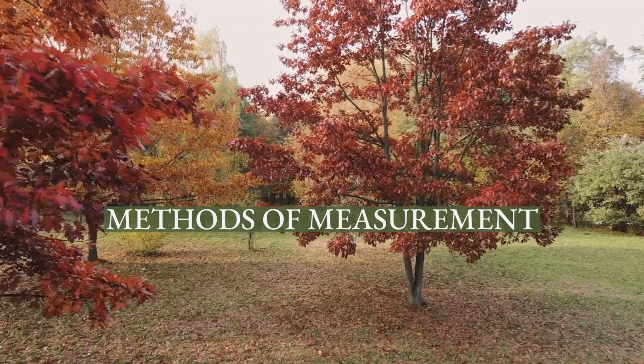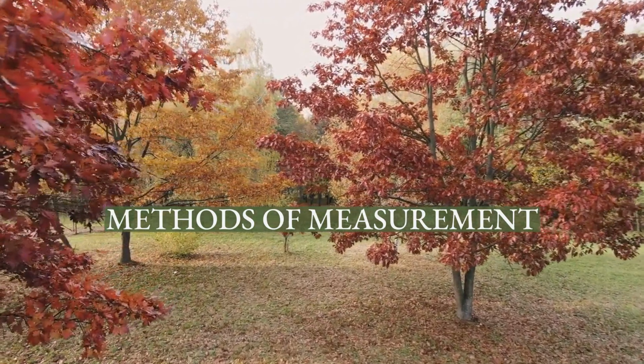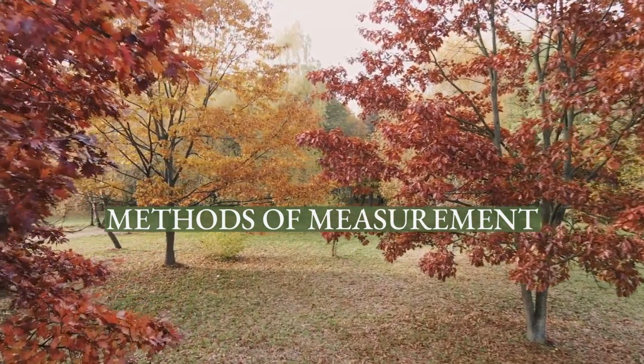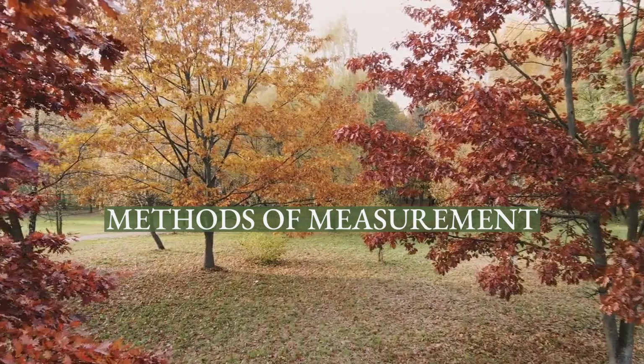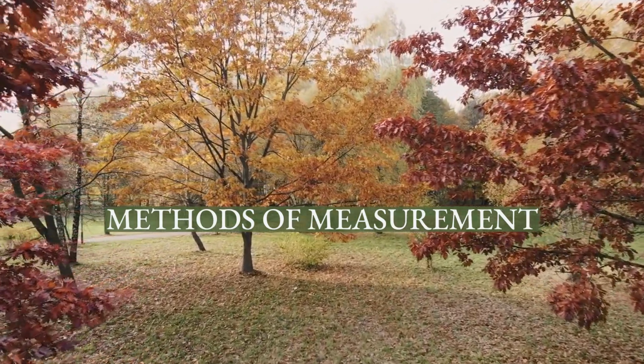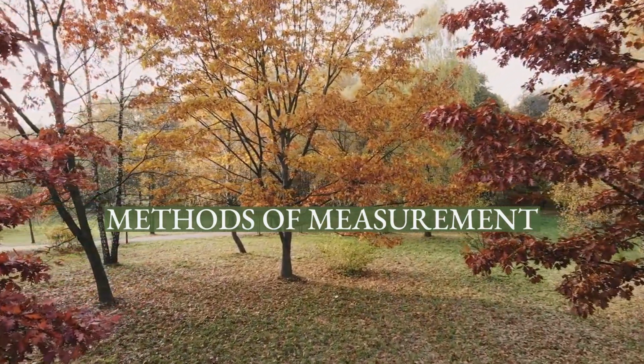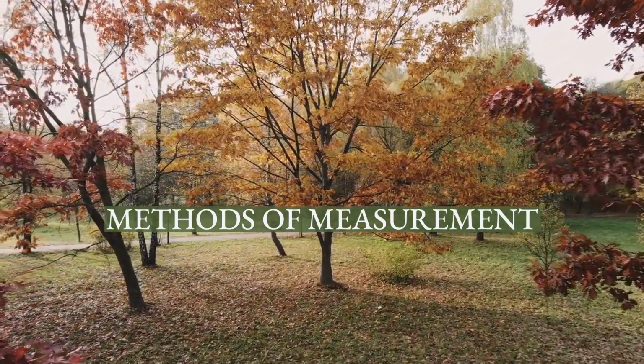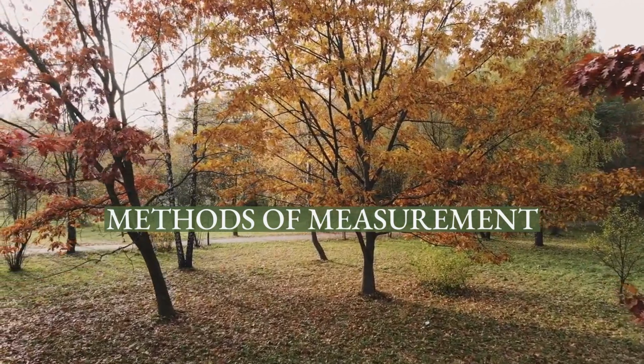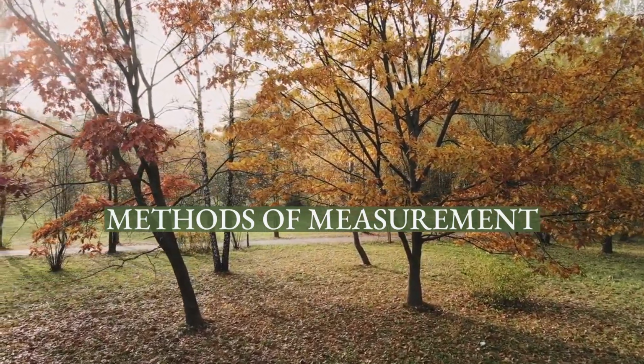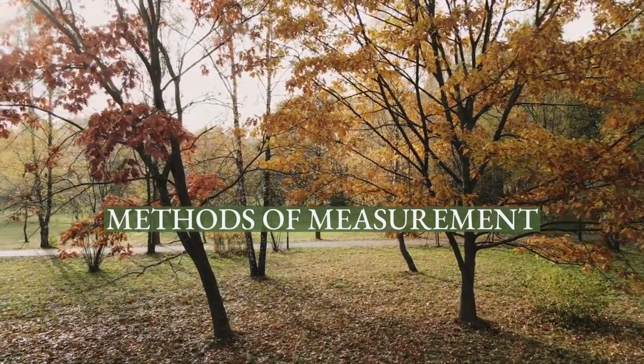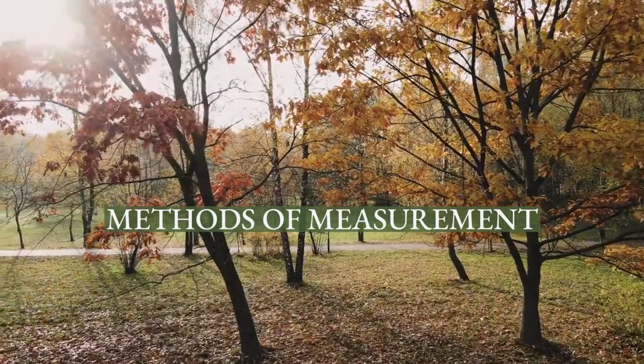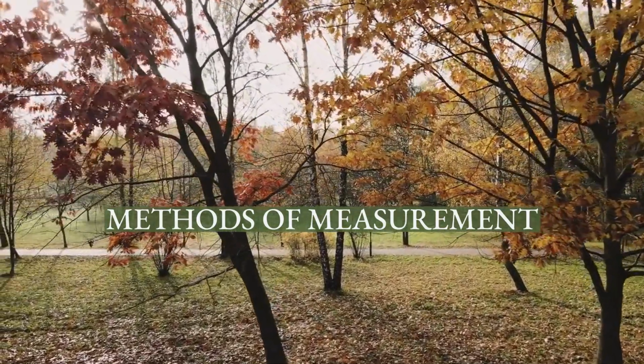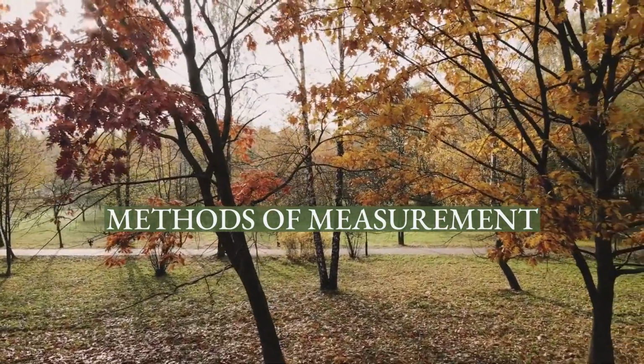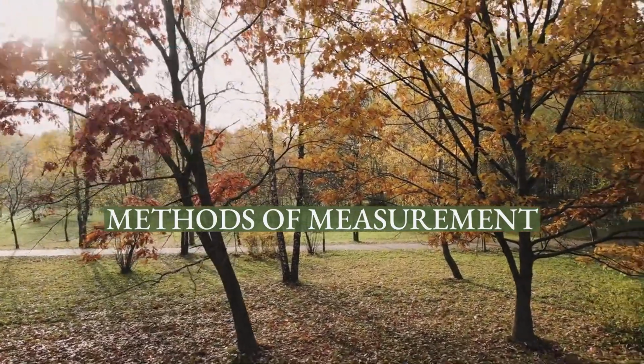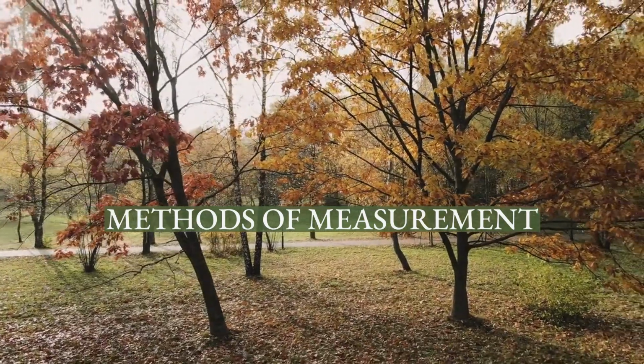Let's now turn our gaze towards methods of measurement and explore the fascinating connections it has to offer. Air changes per hour is a measurement intended to communicate the air change effectiveness of a space's ventilation system. Discussion around the ASHRAE Standard 62, ventilation for acceptable indoor air quality, led to the development of a more direct method of measuring air change effectiveness with the use of a tracer gas. A tracer gas is a small amount of easily detected gas which is mixed with air in order to study airflow patterns.